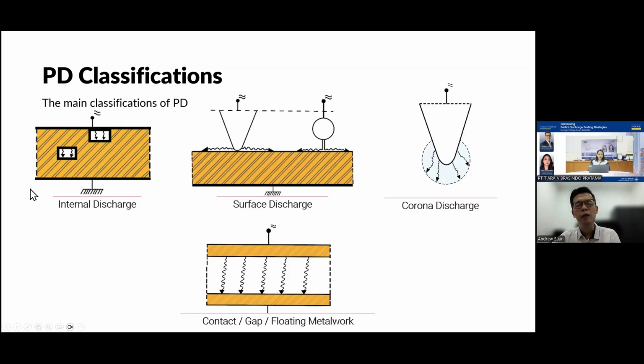In the world of PD, there are a few classifications. The first one is a very common one, internal PD. Internal PD is basically something like a void in the insulation, which we can't really see with our own eyes. This kind of void can be due to poor QC, when the manufacturer makes the insulation and melts the rubber, sometimes air bubbles go in. When the rubber or insulation hardens, a void is formed caused by the air bubble. This actually causes an internal discharge under high voltage stress across the insulation. So this causes internal PD. A lot of time we make use of the transient voltage sensor to pick it up.